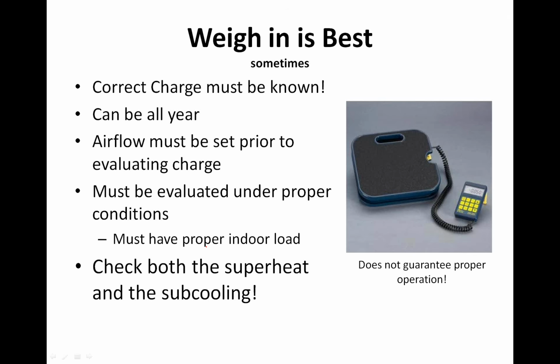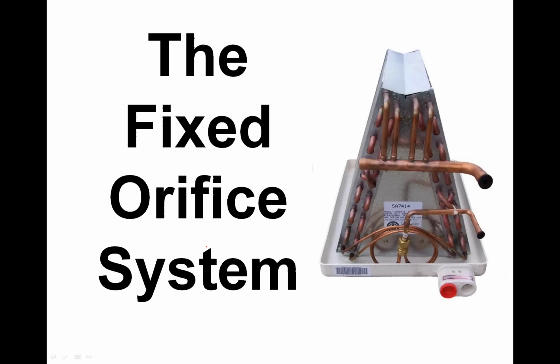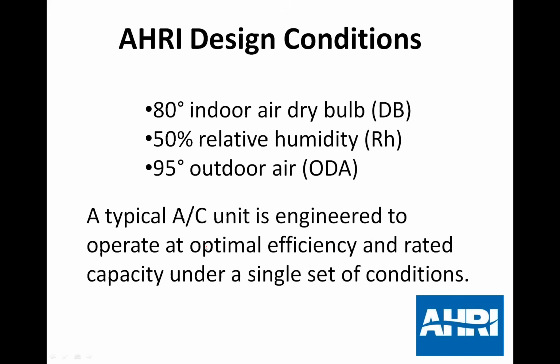We can't just go, well, it's winter time, and I'm going to go ahead and install a system out there, and I'm going to weigh in the gas and how much it takes, and I'll be fine. You got to make sure that you actually go back and properly commission that system and check both the superheat and subcooling. So let's go over the fixed orifice system, and this is the one that's probably more common than anything, and a lot of guys out there still don't know how to properly charge this. So I want to go over some things with this that will help you guys understand how they work.